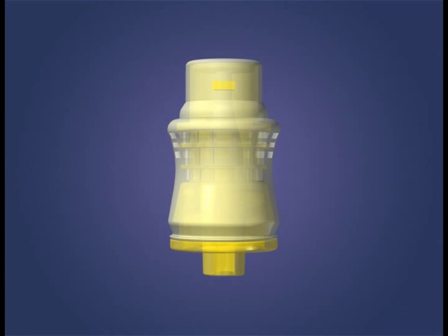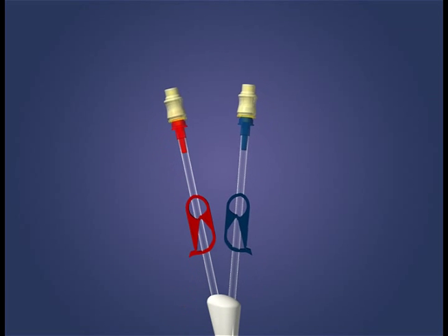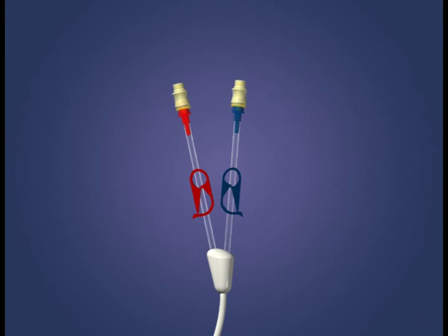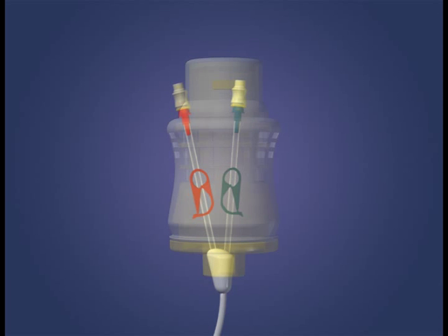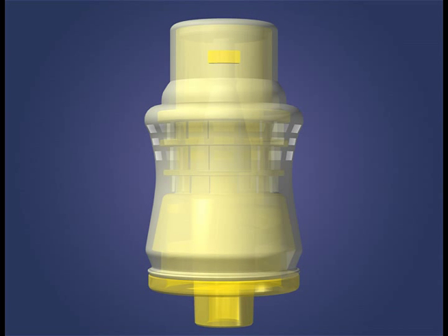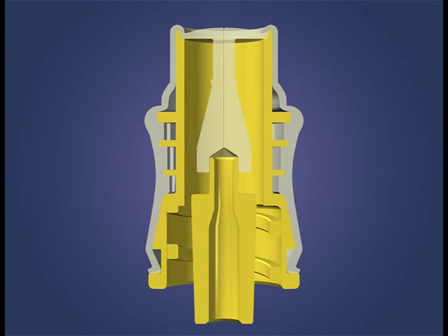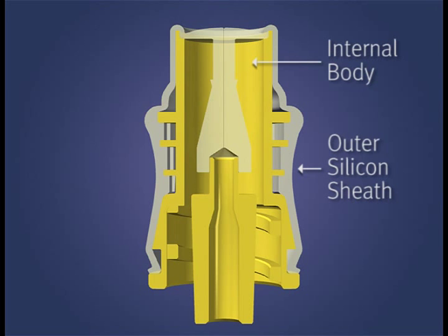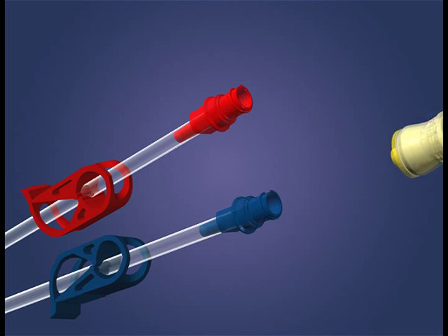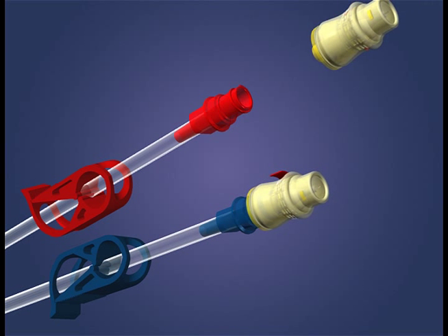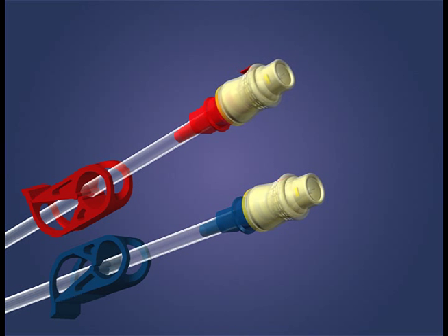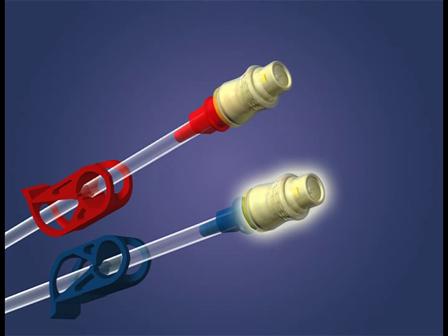The Tego connector is the only catheter protection device available today specifically designed for hemodialysis catheters. The ability of the Tego to prevent contamination of the catheter while performing the hemodialysis treatment is demonstrated in this model. The Tego is made up of two components, the internal body and an outer silicone sheath. The Tego is attached directly to each hub of the central venous catheter, creating a microbiologically and mechanically closed system.